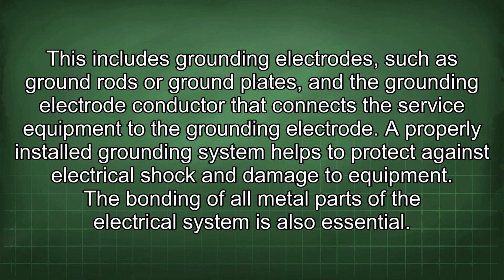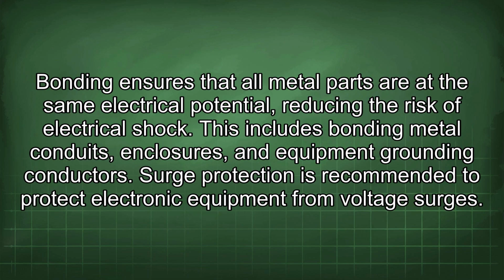This includes grounding electrodes such as ground rods or ground plates, and the grounding electrode conductor that connects the service equipment to the grounding electrode. A properly installed grounding system helps to protect against electrical shock and damage to equipment. The bonding of all metal parts of the electrical system is also essential. Bonding ensures that all metal parts are at the same electrical potential, reducing the risk of electrical shock. This includes bonding metal conduits, enclosures, and equipment grounding conductors.